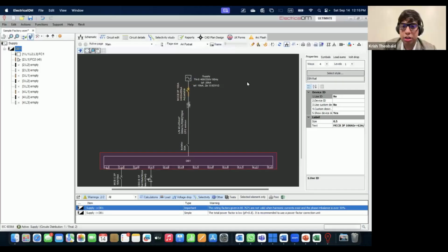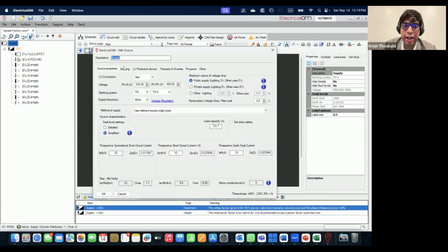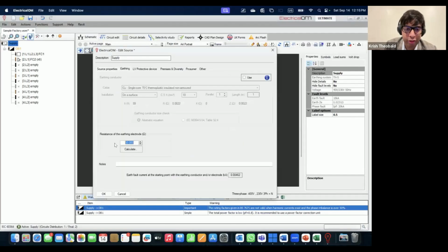As long as you have the relevant earth electrode, anything below to ensure that automatic disconnection facilitates, you can input the earth electrode resistance. But yeah, I change this to TT, and I can add an earth electrode if I want to. And as long as the value facilitates earth fault loop impedance, then no problem.